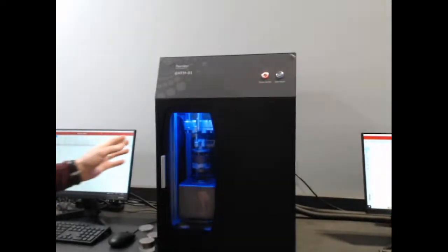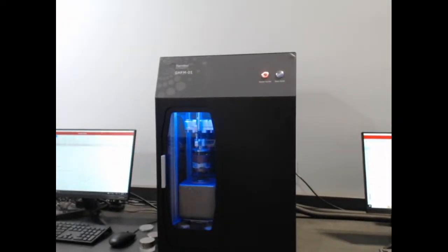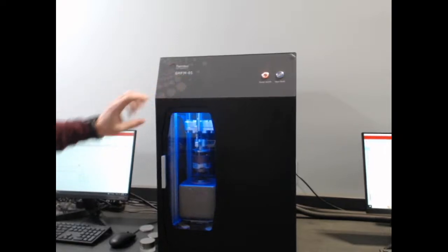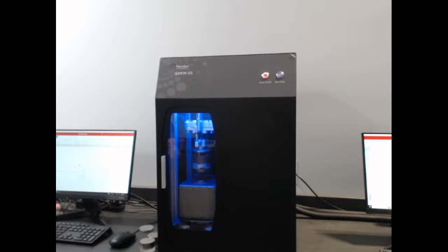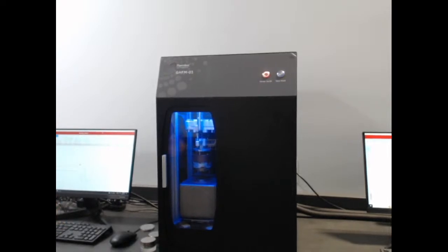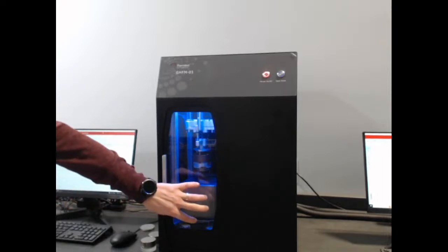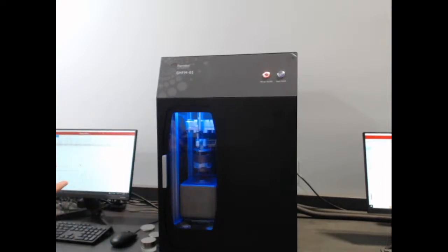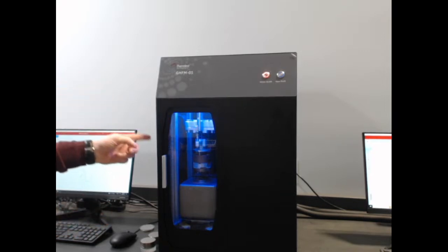This is our guarded heat flow meter, following ASTM E1530. It's a GHFM-01. This is for measuring thermal resistance and thermal conductivity. It's guarded, so it allows for complex structures and layers where we want to ensure one-dimensional heat flow. That guard oven moves up and we have a delta T across the sample and it gives us one-dimensional heat flow. This is from minus 20 to 300 Celsius.